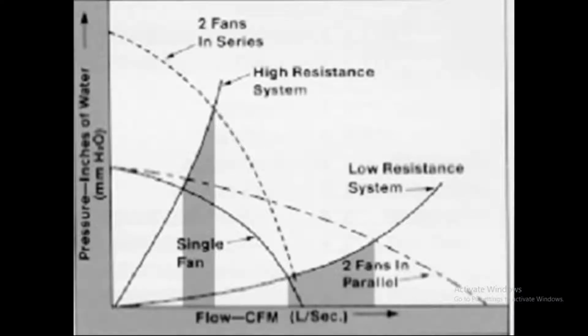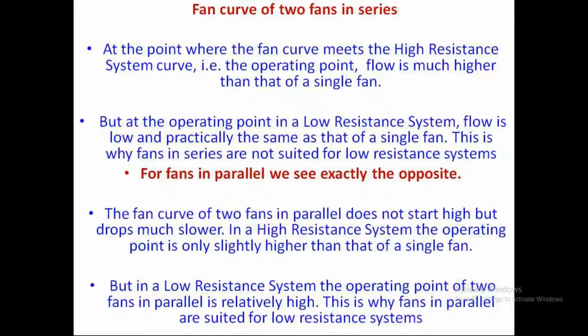Normally, in some of the industries, like a booster fan, they have two fans in series where high resistance is there, and if you want to increase the flow, automatically the static pressure increases when two fans are in series. But in many of the applications in the industries, in the exhaust or in the suction or in the air washer, they have parallel fans where the system resistance is low, and two fans in parallel can give an excellent CFM at a very low static pressure.